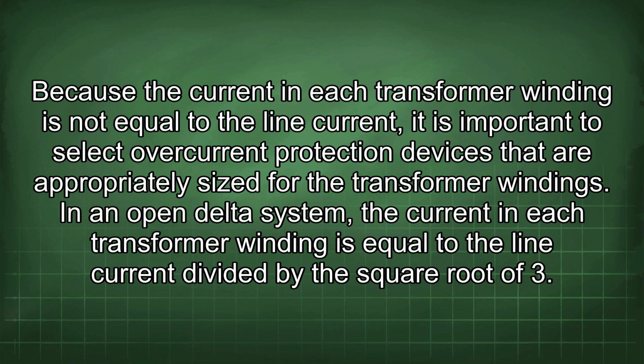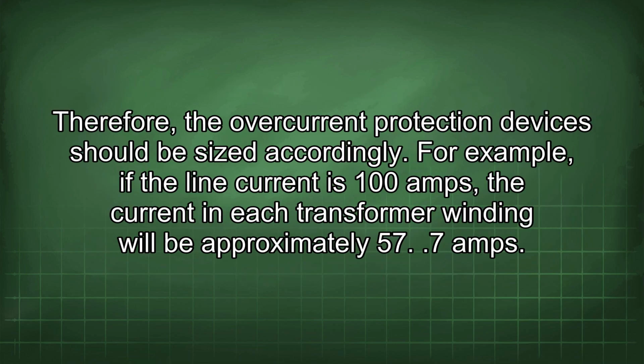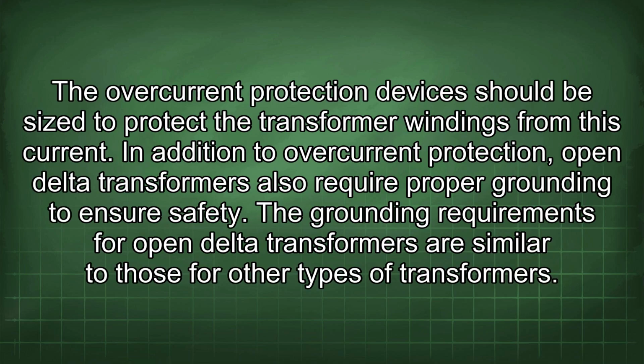In an open delta system, the current in each transformer winding is equal to the line current divided by the square root of 3. Therefore, the overcurrent protection devices should be sized accordingly. For example, if the line current is 100 amps, the current in each transformer winding will be approximately 57 amps. The overcurrent protection devices should be sized to protect the transformer windings from this current.